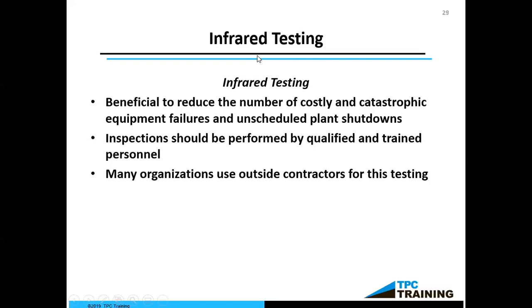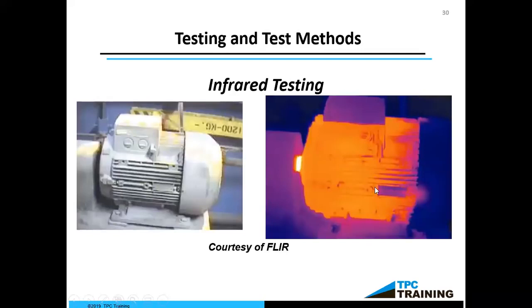But I have mentioned this before about the infrared testing, and if you're not using that currently for your predictive maintenance, then this is a great tool. This is something that gives us a true picture of exactly where our problem is and the extent of that problem. So with infrared testing, you can see immediately in the picture to the right, I've got an issue on the left-hand part of this where it is coupled up to something, and it's probably a bearing issue. So when you can take a picture like that, it's going to give you so much information, and it's just really nice.